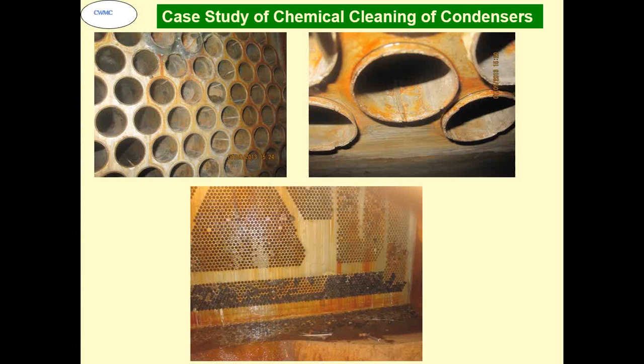Now this is a typical case. These tubes, what you see, are SS304 stainless steel tubes, and you can see a lot of corrosion product inside, reddish in color. In this particular case, the plant had fly ash silos along the cooling water system. Fly ash used to fall inside the cooling water and started choking the condenser tube. Below that, a reducing atmosphere is created. As we all know, stainless steels remain stainless so long as they are in an oxidizing atmosphere. The moment the atmosphere is reducing, it behaves the same way as a mild steel system.